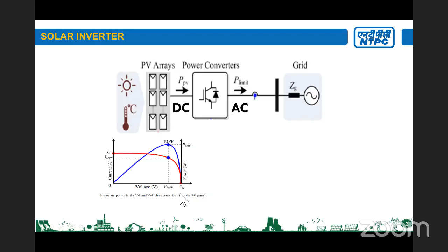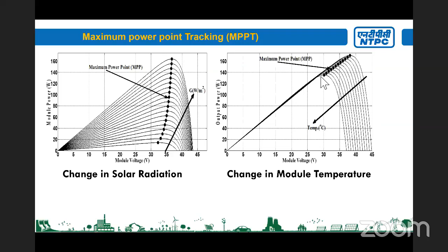So the responsibility I'm mentioning is to operate the PV plant at maximum power point, and this PV graph varies. On the left side, the variation is with respect to solar irradiance, and as the solar irradiance changes, the maximum power point also changes. So if there is any solar radiation change, the system will operate the PV under a different DC voltage so that maximum power can be extracted from the PV system. Similarly, if the temperature of the module varies, the graph also changes, so again it will operate at a different voltage in order to optimize the generation.